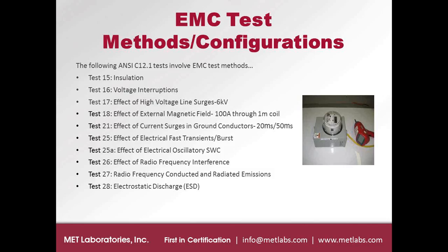As you can see, there's a list of the EMC-specific tests that are called out in ANSI C12.1 as well as ANSI C12.20. Now, if you're an equipment manufacturer, you may have come across some of these tests because most of them are required as a part of CE marking. But some tests stand out because they are only ANSI specific. Those are test number 18, effect of external magnetic field, and test number 21, effect of current surges in a ground conductor.